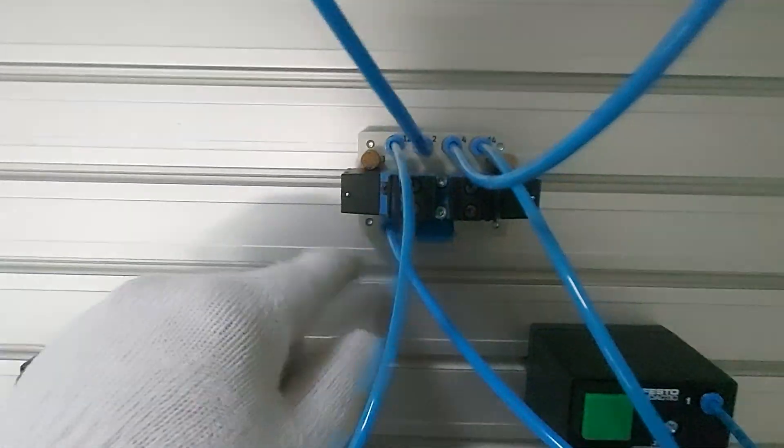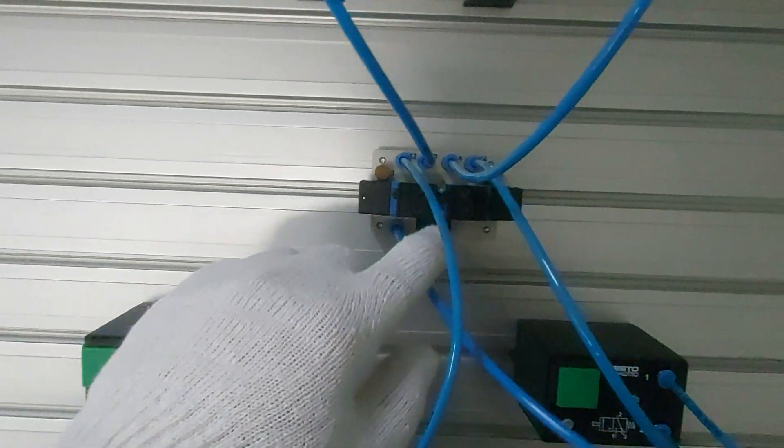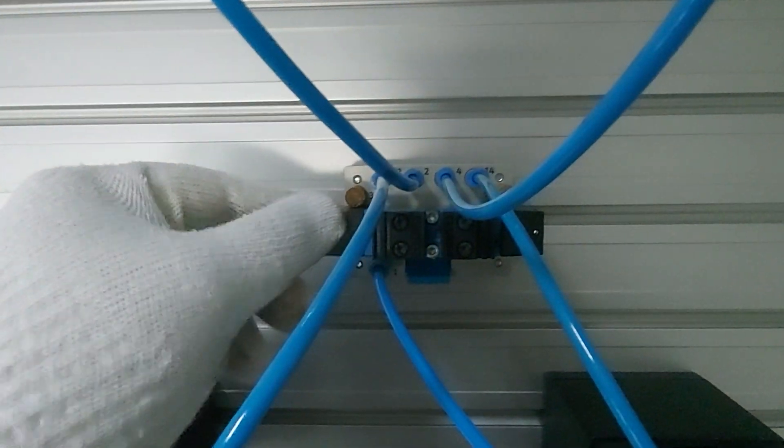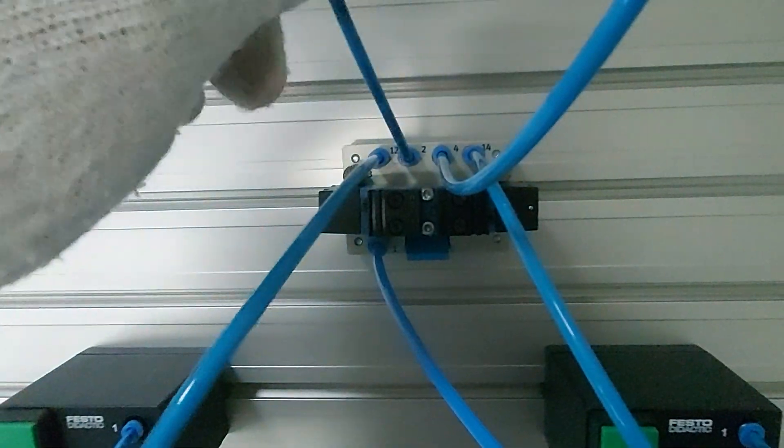As we discussed, even numbers are the output. And 1-2, this is the supply for 2. Because this valve doesn't operate by a button or a selector. It operates by compressed air. So you have to give it supply 1-2 to activate the 2.